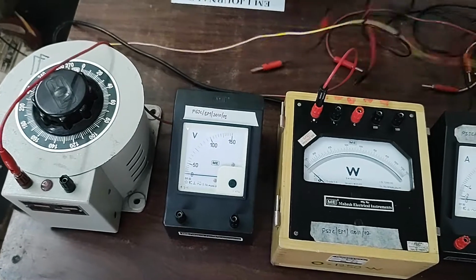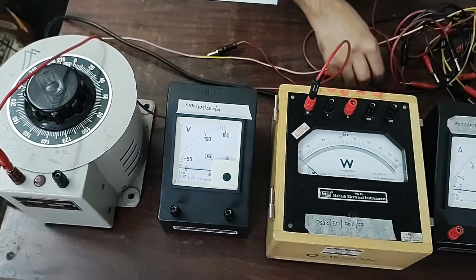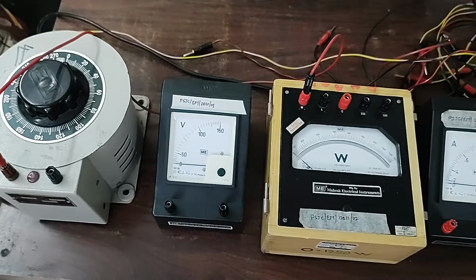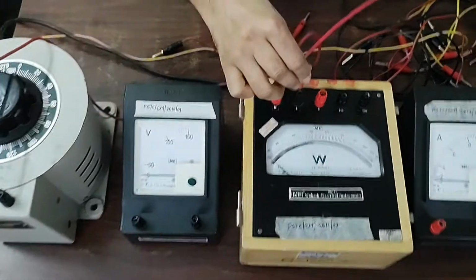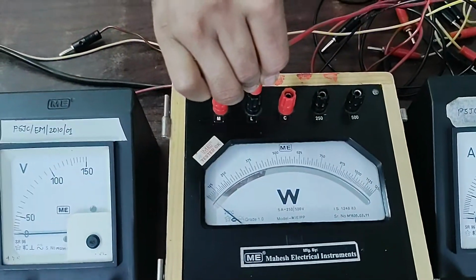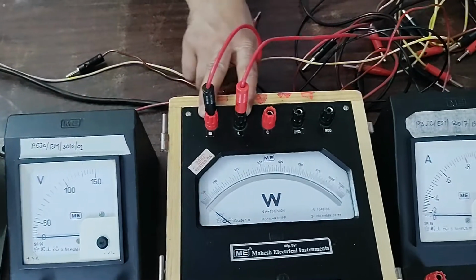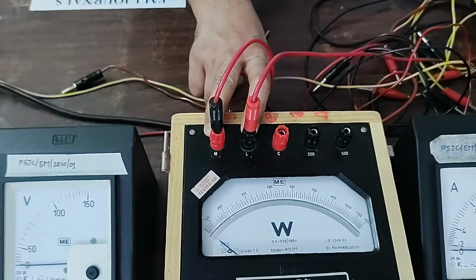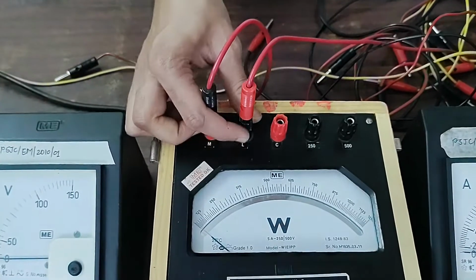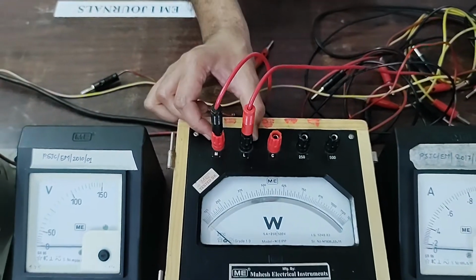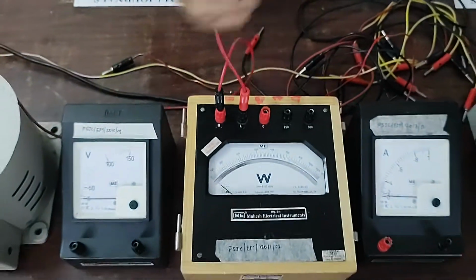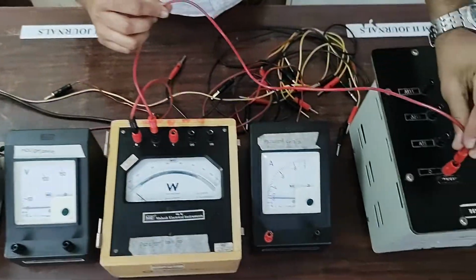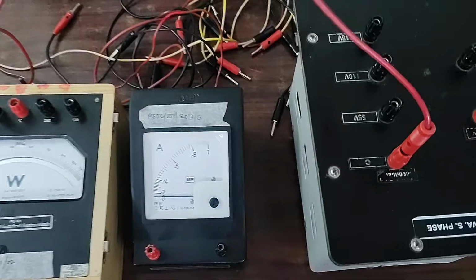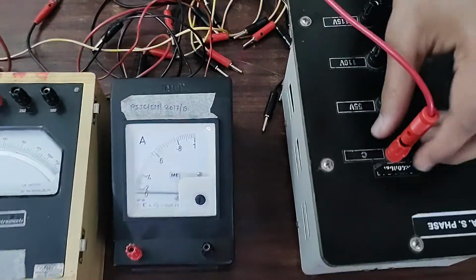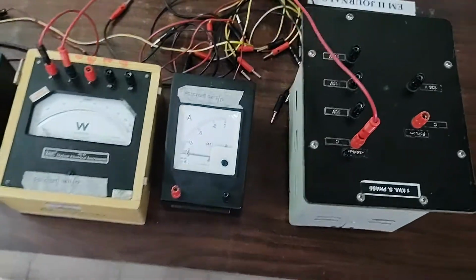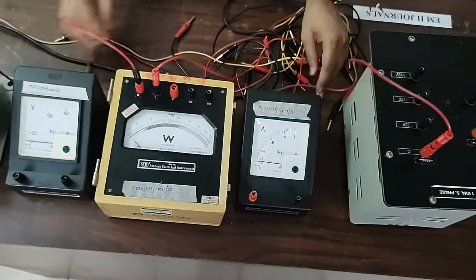Next, we have to connect a wire at the L terminal, and as we know, M and L are internally connected. Mains and L terminal are internally connected. So this is a current coil. So from the L terminal we have to connect it across the primary winding of the transformer, across the phase of the primary. So this is one part of the connection.